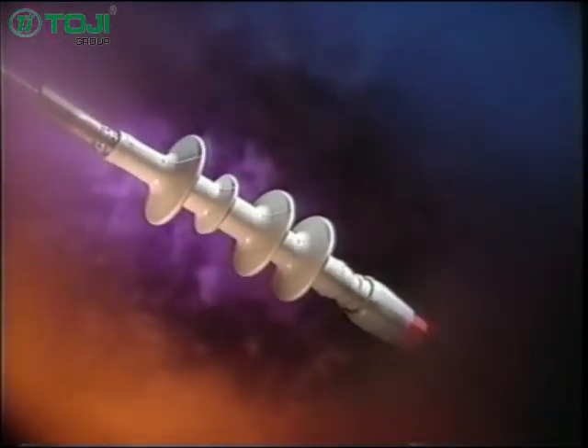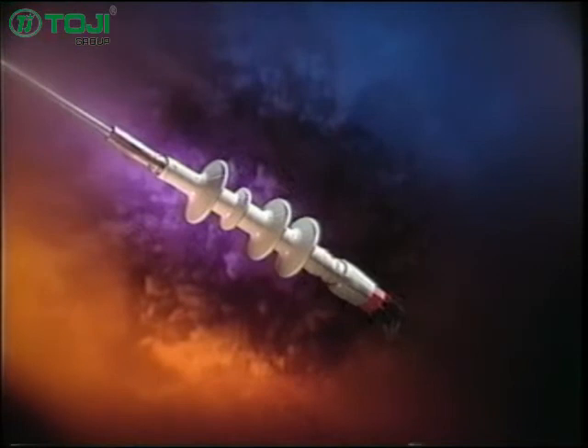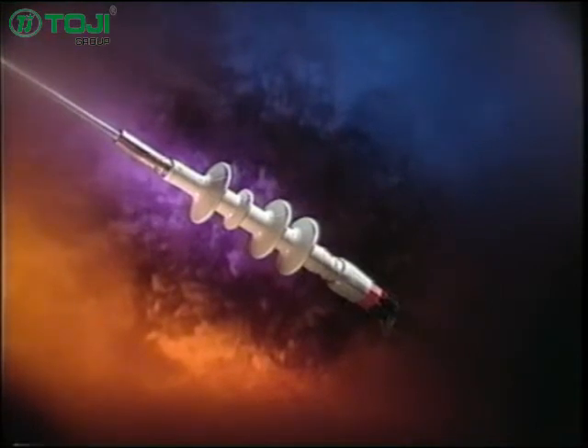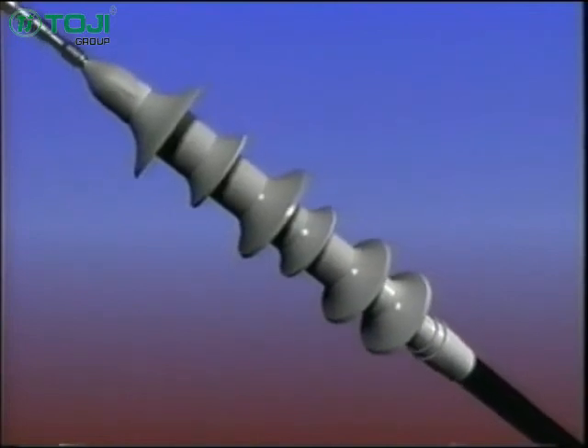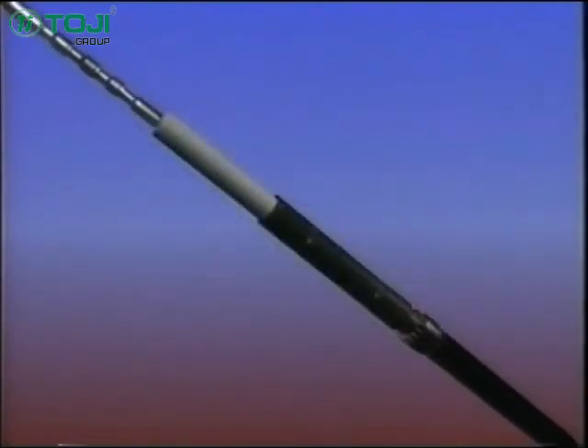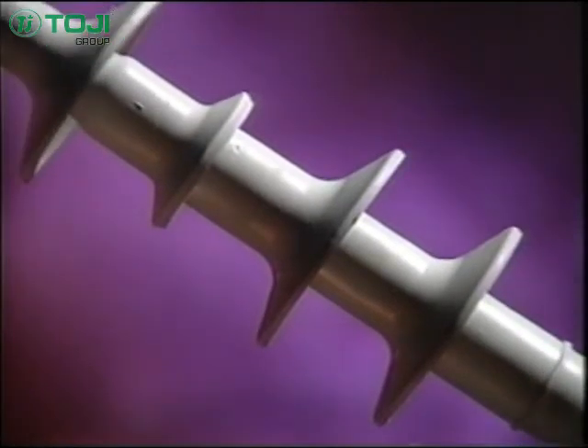Given all the features and benefits, there should be no doubt about the advantages that the Cold Shrink silicone rubber Quick Term 2 termination kits offer. Advanced design: the low-profile, high dielectric constant stress relief tube allows maximum electrical field distribution and lowers the overall surface stress. Our silicones have superior hydrophobic properties with the ability to regenerate their hydrophobicity under high stress conditions. 3M silicone rubber stands up to UV exposure, maintaining its surface integrity. The silicone surface is also less affected by moisture and airborne contaminants.